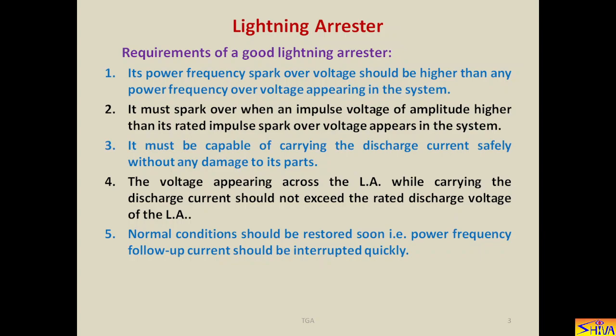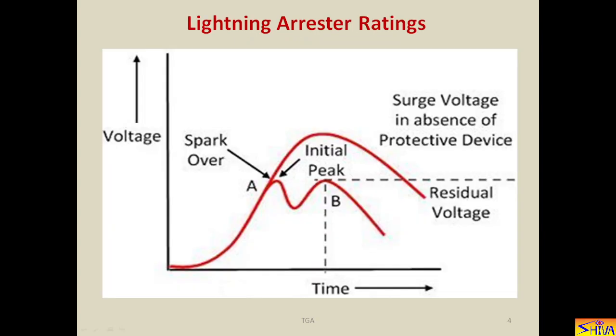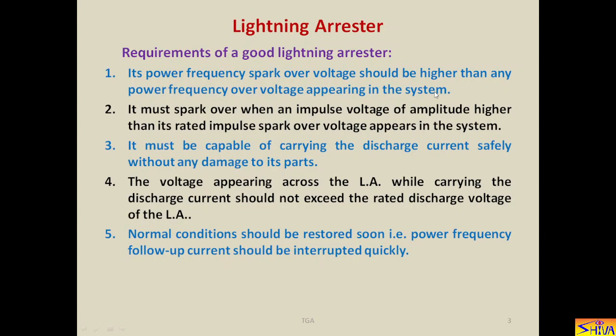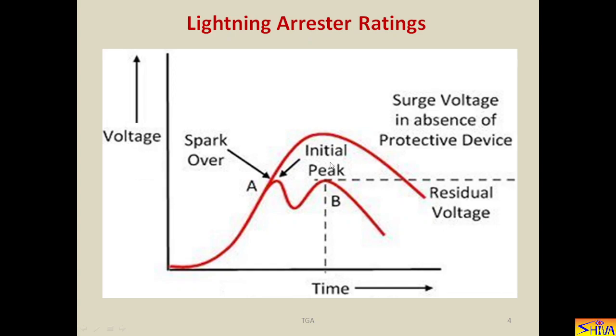So in order to restore the normal condition, the path should be interrupted as quickly as possible. So that is the fifth requirement of lightning arrestor. Now here I am showing the different ratings of the lightning arrestors, that is corresponding to the impulse voltage. So this is the surge voltage in absence of protective device. So at this point the lightning arrestor is sparking over. So this voltage is called as impulse spark over voltage of the lightning arrestor.